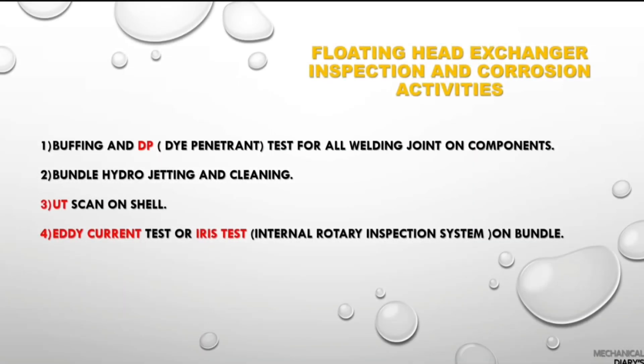Once all components are removed, you must perform all welding joint buffing and DP (dye penetrant) test — you will find weld cracks or defects from this DP test. Then do tube bundle hydrojetting to clean the internal surfaces. Next, perform UT (ultrasonic thickness) scan on the shell to know the shell thickness. Then eddy current and IRIS tests are done on the tube bundles to determine tube wall thickness.